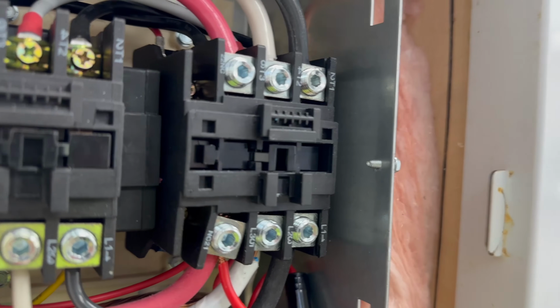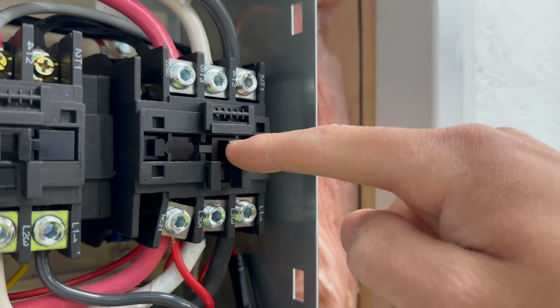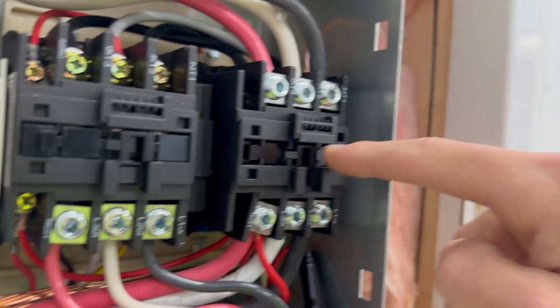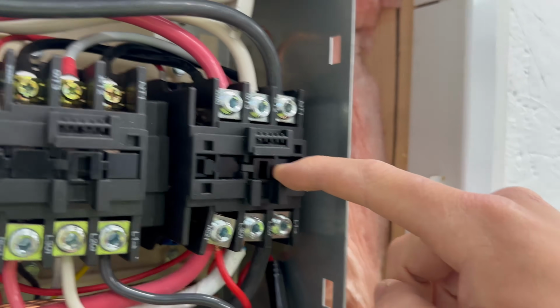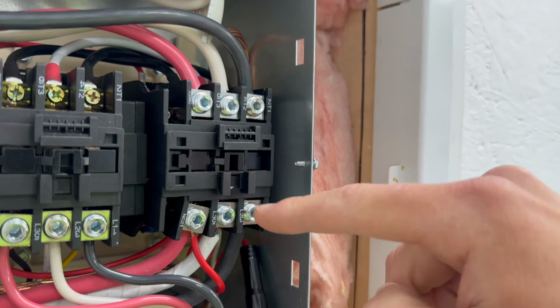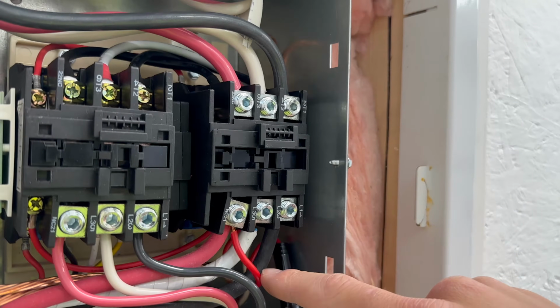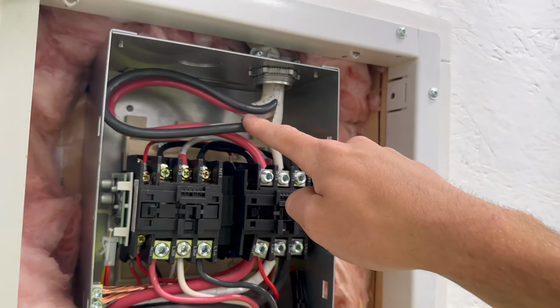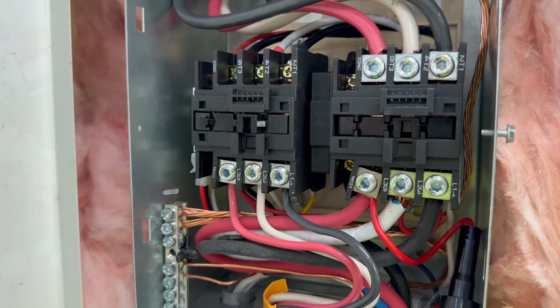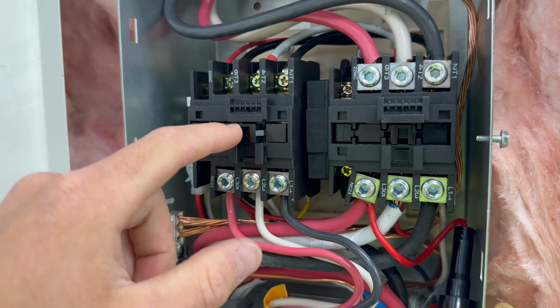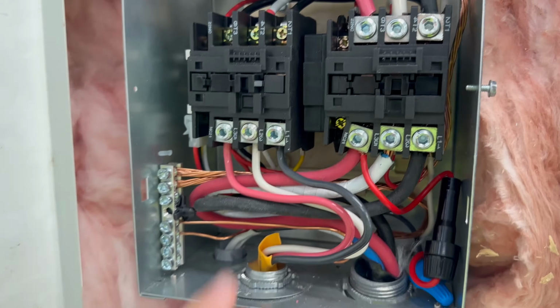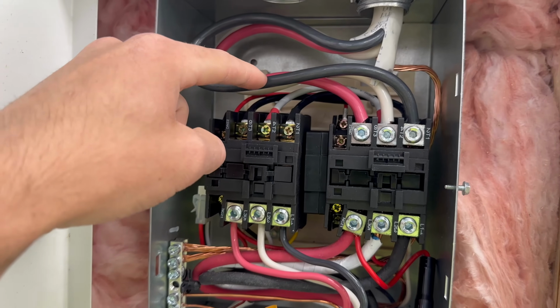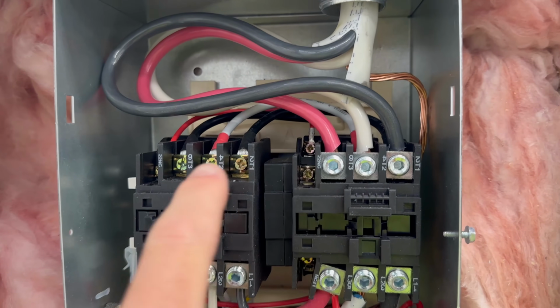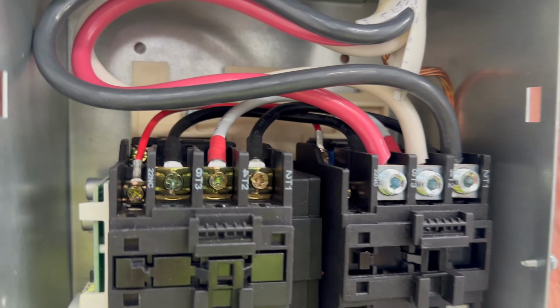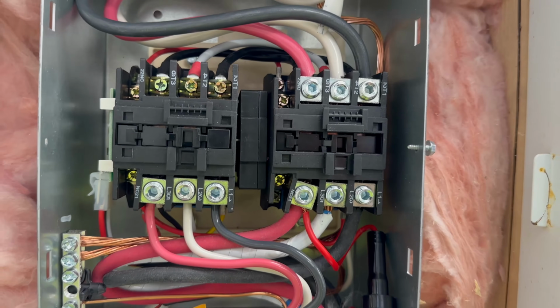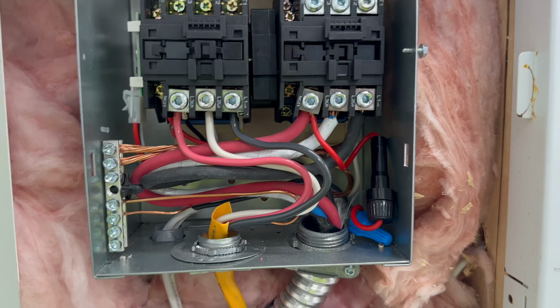And you can see that this contactor is pulled in right there, versus this one isn't. This one's pulled in because right now it's powered off BC Hydro. There's a set of contacts in there that when this pulls in, it will connect each side to each other. So right now the power is coming from BC Hydro and going out on the load side into this panel. However, you can see this side is not pulled in and it is left in the open position, meaning that these wires are not connected to this other side. This side up here and this side over here will always be connected together because there are jumpers going between. It's whether the contacts are open or not which decide what power source it's coming from at the bottom.